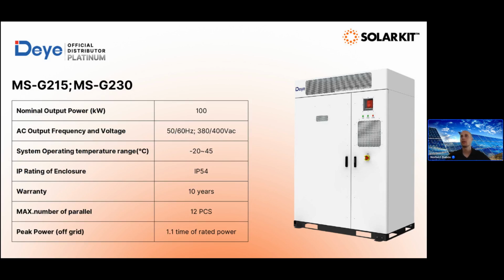And here is the info about the parameters. So you have 100 kilowatt PCS inside, so you can connect the AC cable. It's also a 3-phase 4-wire connection in 400 volt AC, so the regular low voltage AC grid, not the high voltage like the 800. It can work from -20 to 45 degrees because it's AC coupled. IP rating IP54. Also 10 years of warranty, and you can connect 12 pieces together to have a larger capacity and a larger AC output. That's over 1 megawatt of AC and 2 megawatt of ESS capacity. So this is the AC coupled ESS.